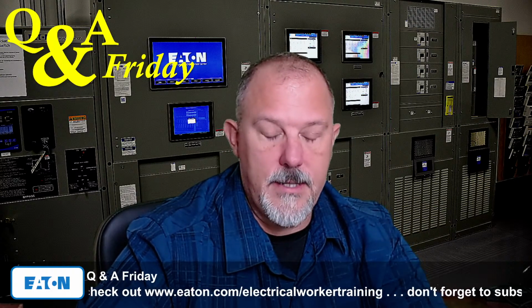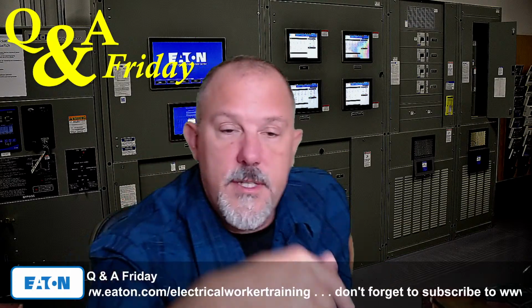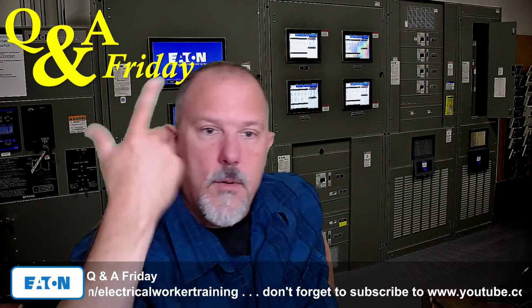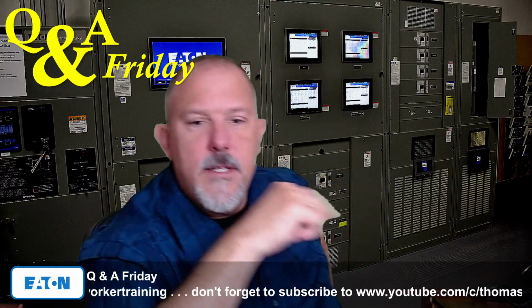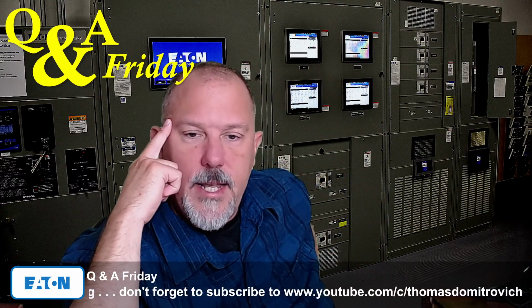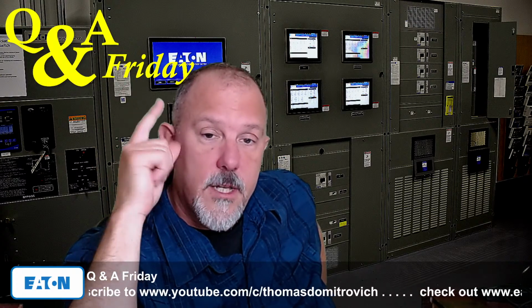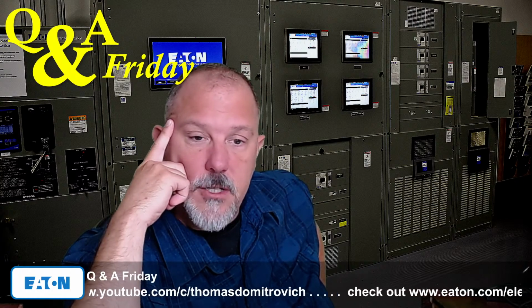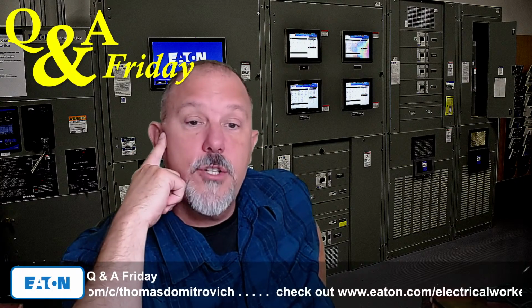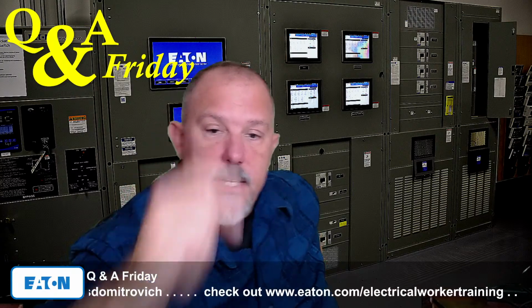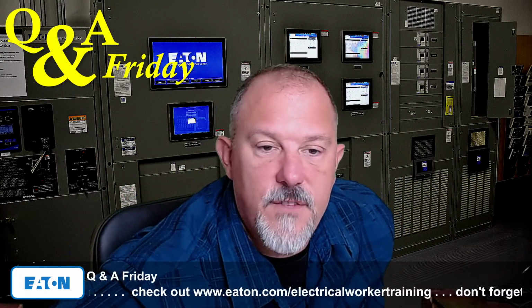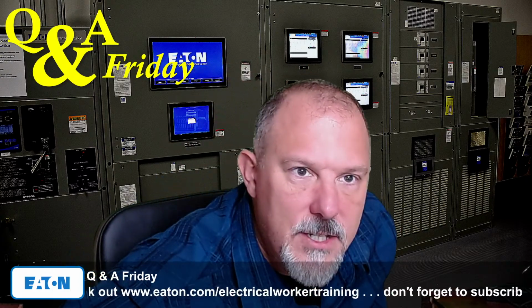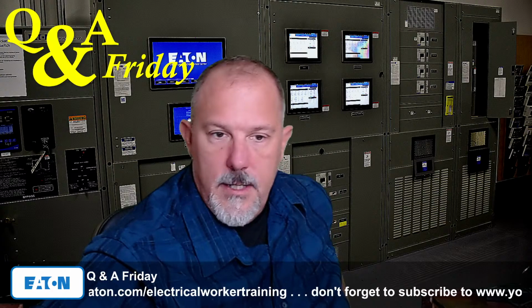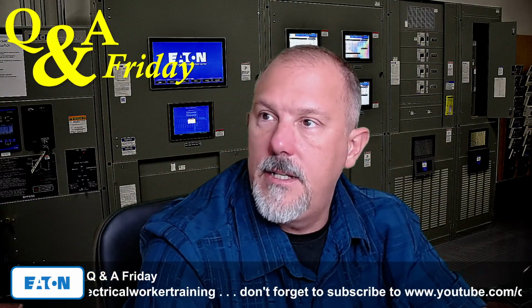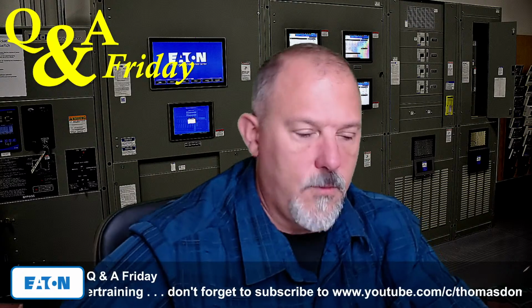I sent the question down to Nick Cluse, who is the product line manager. Eaton's double door safety disconnect switches don't say in the literature if they can be considered suitable for use as service equipment. Also, one challenge with specifying them just based off of seeing a photo is they are taller, making one have to adjust to not exceed the 6 foot. So the product that JW is talking about is the Eaton double door safety switch.